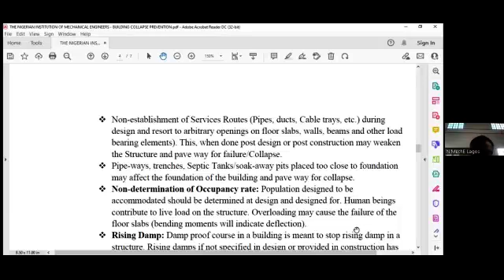Now, non-establishment of services routes, pipes, ducts, cable ways etc. during design leads to arbitrary openings on floor slabs, walls, beams, and other load-bearing elements. When done post-design or post-construction, this may weaken the structure and pave the way for failure or collapse. Just because you want to move a pipe, you open the wall, or to take a drill, you open the floor. Some pipes are big, carrying chilled water, particularly pressurized pipe work, which moves with force and vibration, affecting the structure.